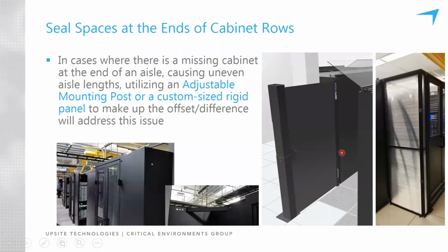So this is the unique scenario, right? Sealing spaces at the ends of the cabinet rows. We're not quite yet talking about doors. This scenario is more commonly found in retrofit applications where containment perhaps was an afterthought. Because most vendors' door designs require that the aisle end cabinets be in alignment, or on the same plane, for the doors to attach and install properly, even the slightest offset can make the installation a little bit tricky and will require some means of dealing with and sealing the space.